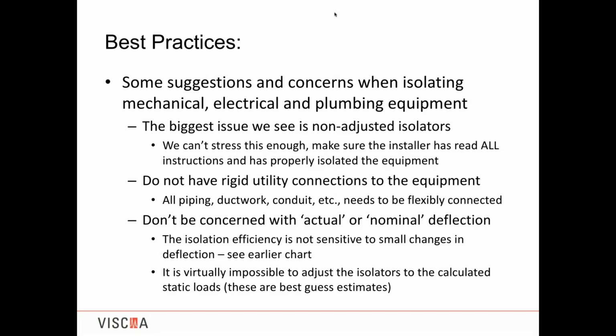And the next biggest issue we see are the rigid utility connections. Piping, ductwork, conduit to the equipment. I can't stress enough how, especially on pumps, flex connectors must be on there. Something has to be flexibly connected. If you're rigidly attached to the next series in the system, and that next series is non-isolated, you have a rigid path for your vibration to go through, and it doesn't matter how many inches deflection you have underneath your pump, say, you're moving that vibration downstream.